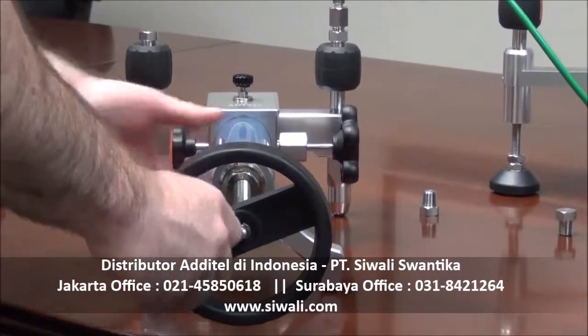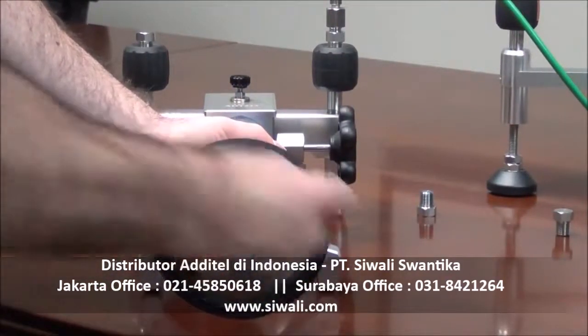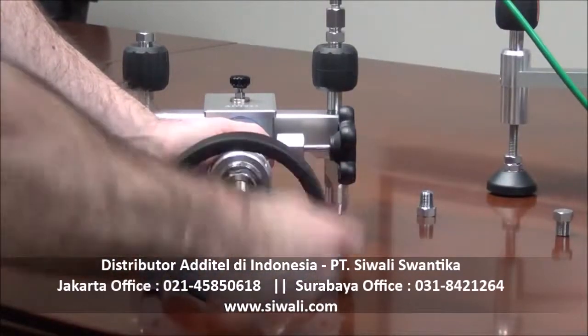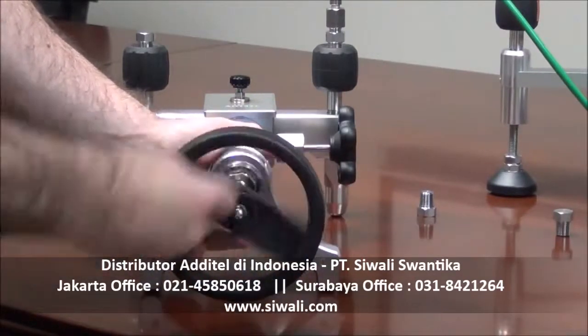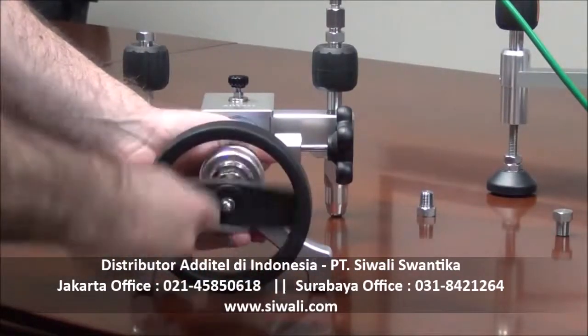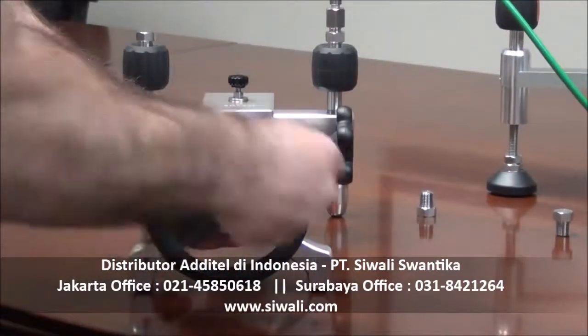Then I'm going to open up the vent valve and push the screw press all the way in. This is now pushing any gas back out of the system. When I get to the end, you probably won't be able to see it, but there will be some bubbles that you'll see come up. There are a few that come up in the cylinder there.